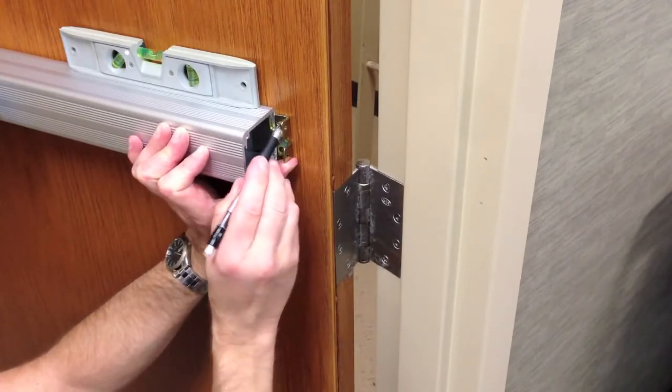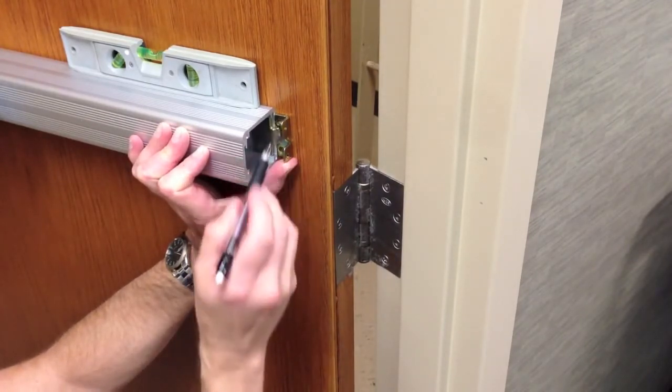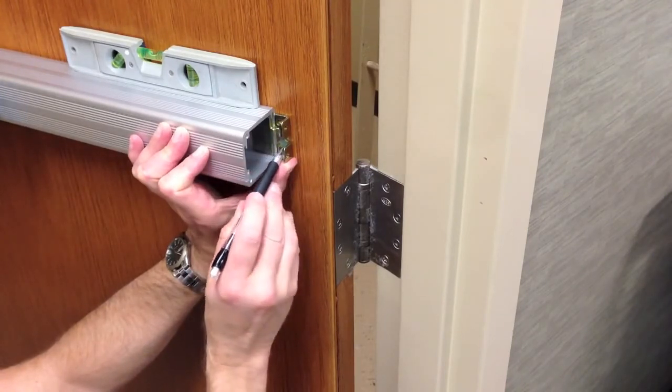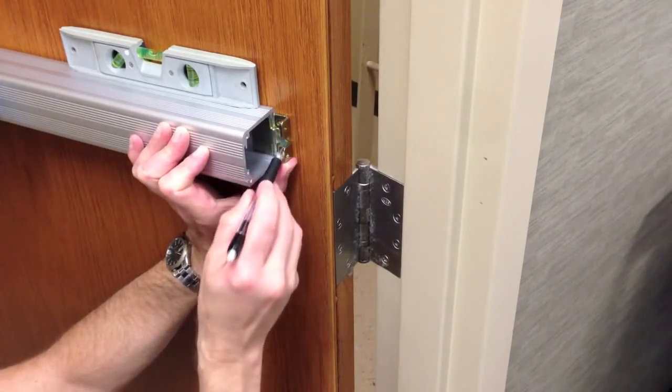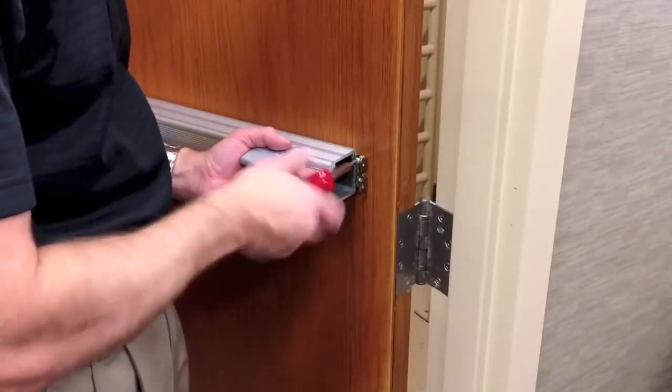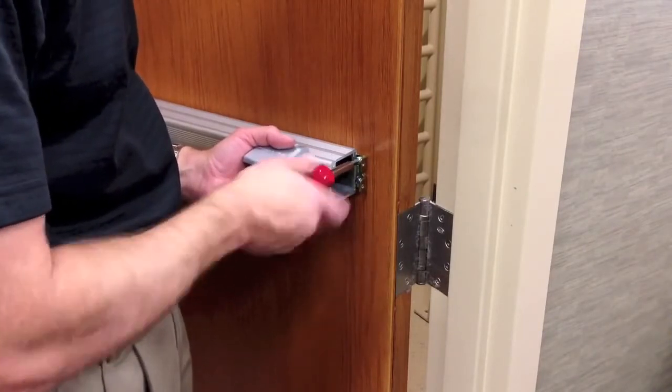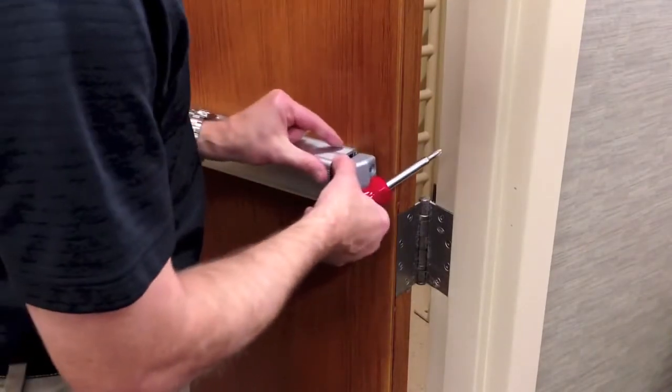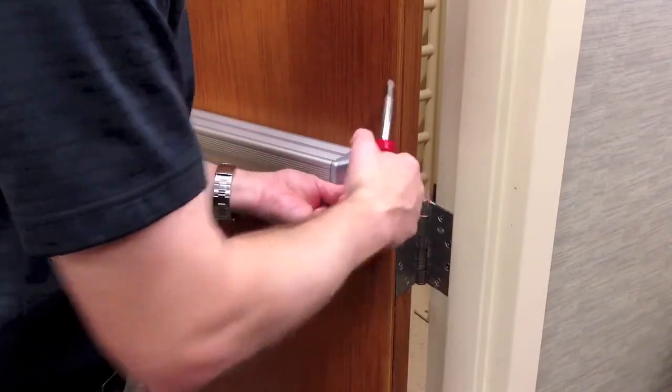Remove the exit device from the door and drill and tap the holes. The preparation chart in the instructions will guide you. Reinstall the exit device and install the end cap bracket and end cap with the provided screws. Use the screw chart to identify the proper screws.